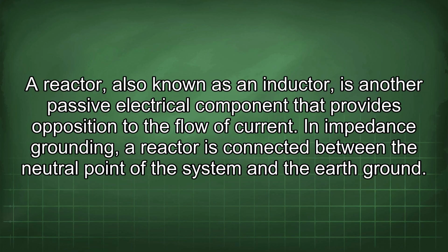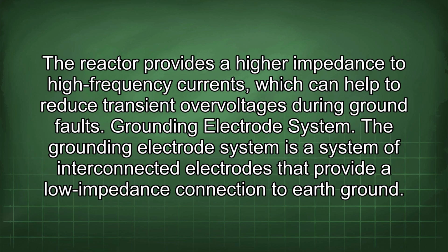Reactor. A reactor, also known as an inductor, is another passive electrical component that provides opposition to the flow of current. In impedance grounding, a reactor is connected between the neutral point of the system and the earth ground. The reactor provides a higher impedance to high-frequency currents, which can help to reduce transient overvoltages during ground faults.